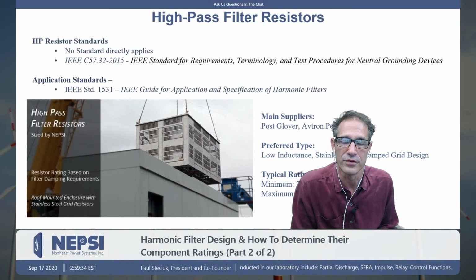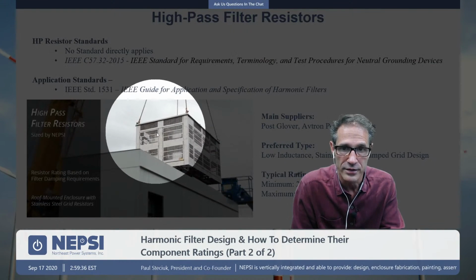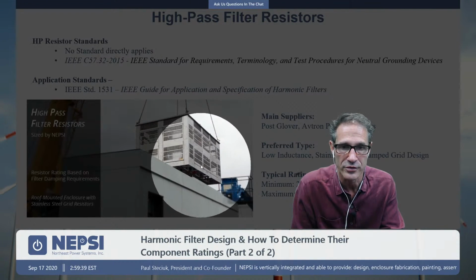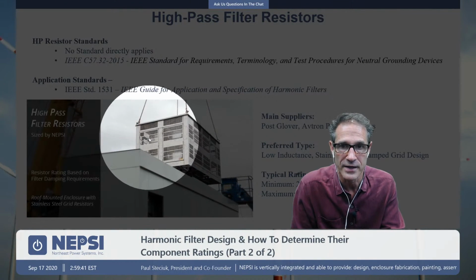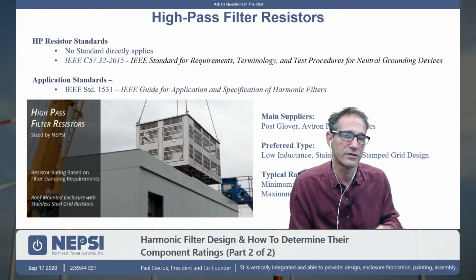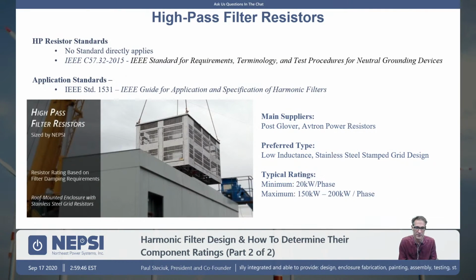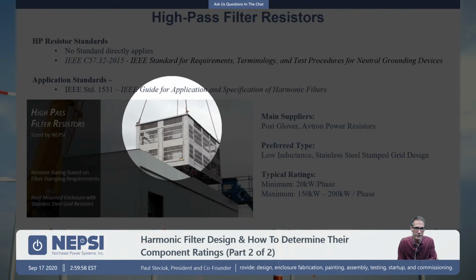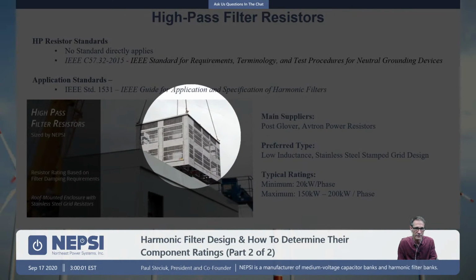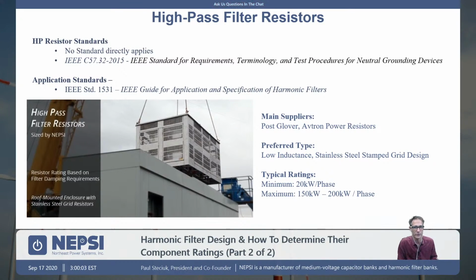High-pass filter resistors. Here we are putting a set of high-pass filter resistors on top of one of our enclosures. This is a stainless steel enclosure. The reason it's stainless steel is that the enclosure itself can get hot up there. We don't want paint on there that can blister or turn colors, turn brown because of heat. So we're using a stainless steel enclosure. There are no fans for this. We're looking at using just natural ventilation to keep the resistors cool. So this is our standard practice is to park them up on top.